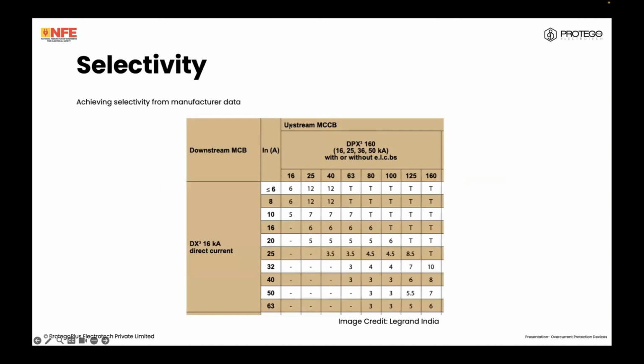Obviously this is a complicated process, so a manufacturer will give us this data. They will say, this is from Legrand by the way, for this MCCB and this MCB, selectivity is achieved to this value. So for a say 100 ampere MCCB and a 16 ampere MCB downstream of it, you will achieve total selectivity up to 16 kiloamperes. If it is a 32 ampere MCB downstream, selectivity is achieved up to 4 kiloamperes. These values are available for all manufacturers. Some manufacturers even have specialized software where you can do this.